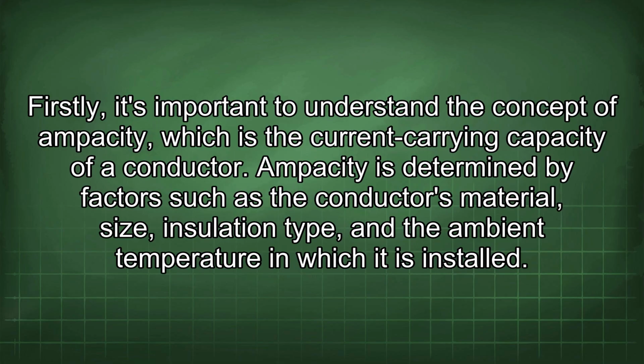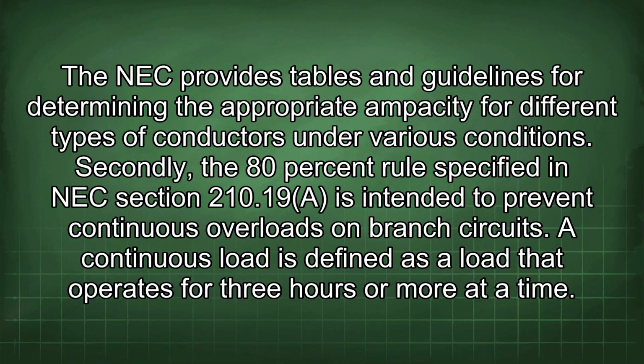Firstly, it's important to understand the concept of ampacity, which is the current carrying capacity of a conductor. Ampacity is determined by factors such as the conductor's material, size, insulation type, and the ambient temperature in which it is installed. The NEC provides tables and guidelines for determining the appropriate ampacity for different types of conductors under various conditions.